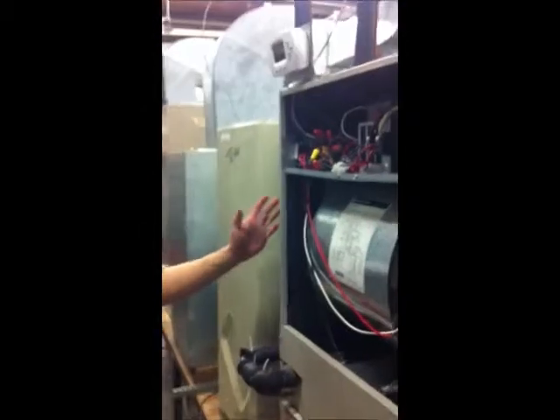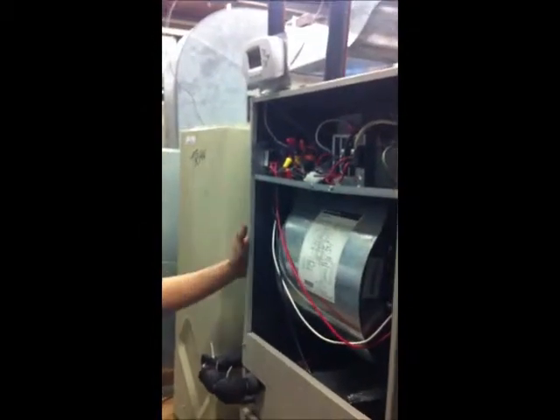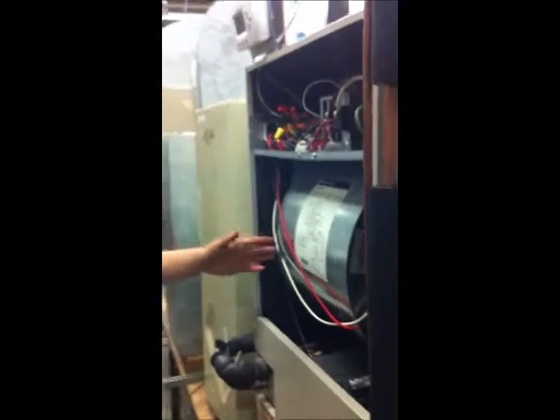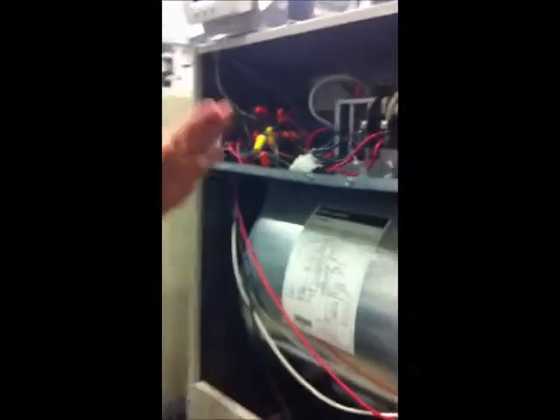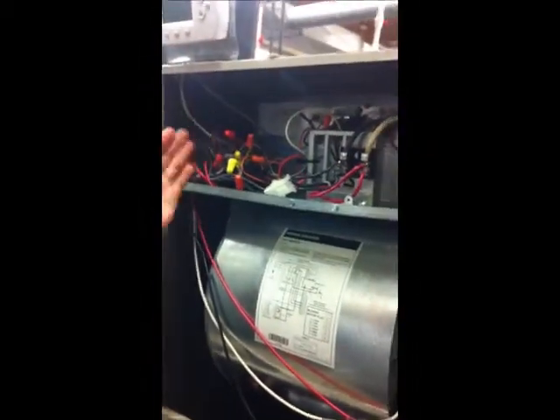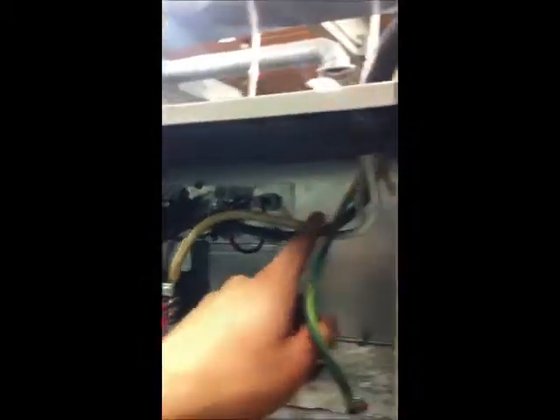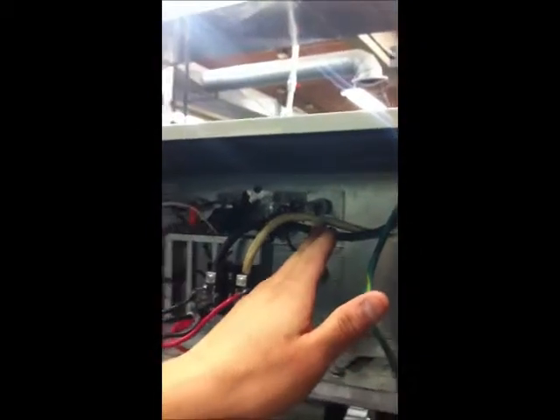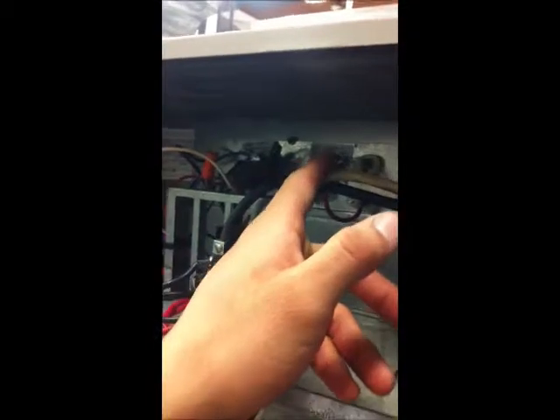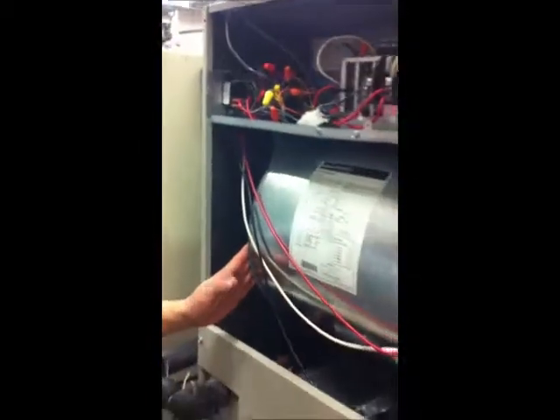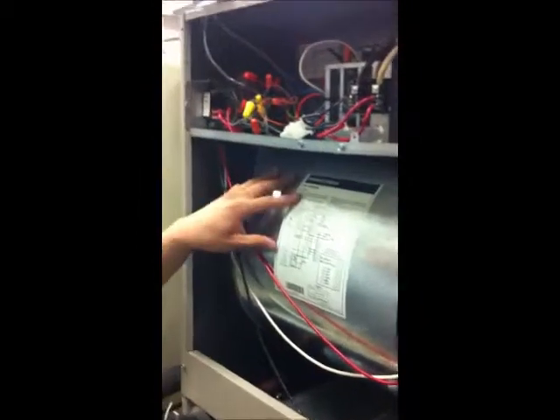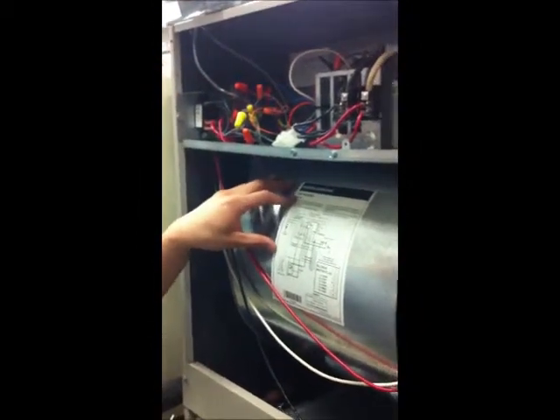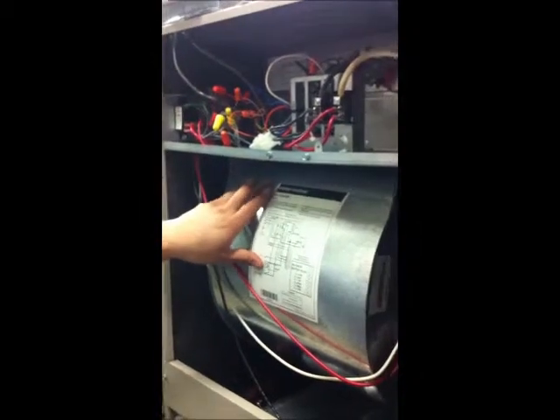Now we got ourselves the exposed internals of the furnace. We can see we have the wiring, we have our thermostat wiring, our sequencers, our line in, which is a 208 volt system, the black wire, and this is our neutral wire. And down here we got our blower motor, which we already tested and it's not coming on when we press the fan on and emergency heat.